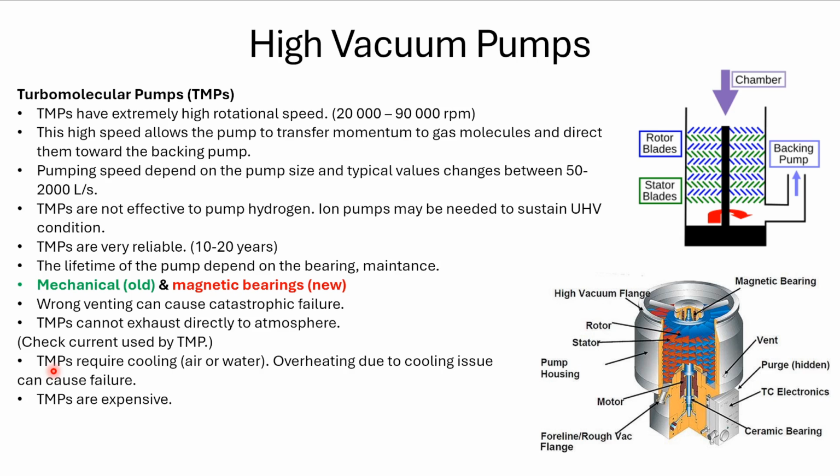If you have a turbo pump and, for instance, a Rotary-Vane pump, and if your Rotary-Vane pump is not working properly, then you can check the current that is used by the turbomolecular pump. If the current is high, more than 1 ampere, then you can say that your Rotary-Vane pump is not working properly, or you have to change the tip seals of the scroll pump. And the main issue of the turbomolecular pumps is that they are extremely expensive.